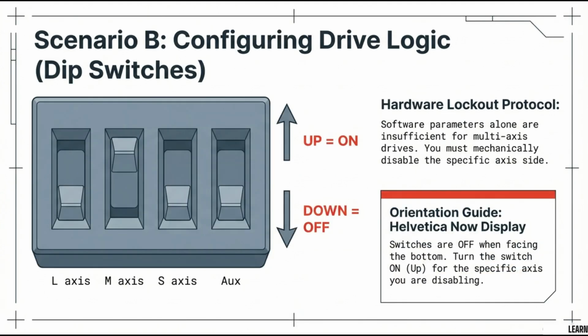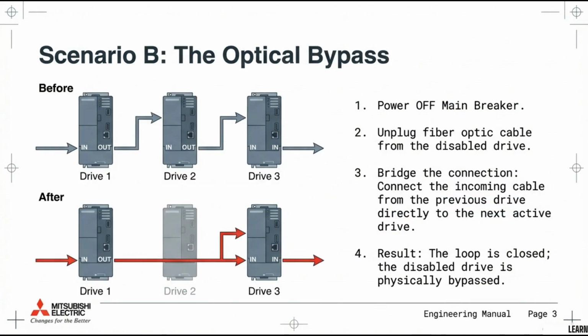For multi-axis drives, software parameters are insufficient. You must also configure the drive logic using the dip switches for hardware lockout. Turn the switch ON or UP for the specific axis you are disabling. The optical bypass procedure for scenario B involves powering off the main breaker and unplugging the fiber optic cable from the disabled drive. Bridge the connection by linking the incoming cable from the previous drive to the next active one to close the loop.